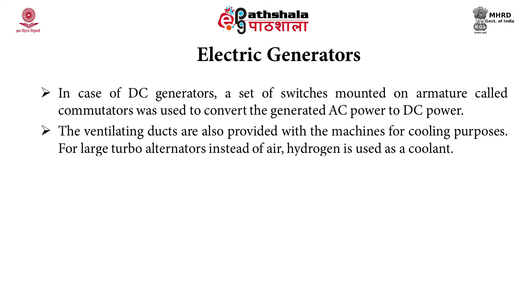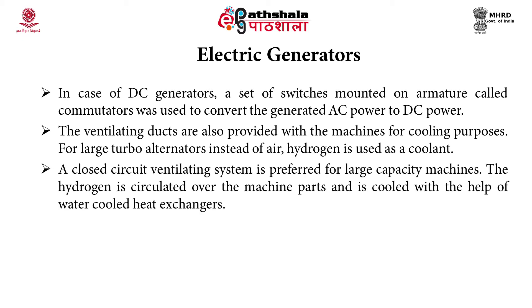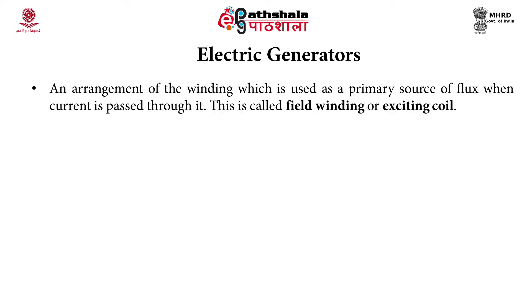Ventilating ducts are provided with the machines for cooling purposes. For large turbo alternators, hydrogen is used as a coolant instead of air. A closed circuit ventilating system is preferred for large capacity machines, where hydrogen is circulated over the machine parts and cooled with the help of water-cooled heat exchangers. An arrangement of winding used as the primary source of flux when current is passed through it is known as field winding or exciting coil.